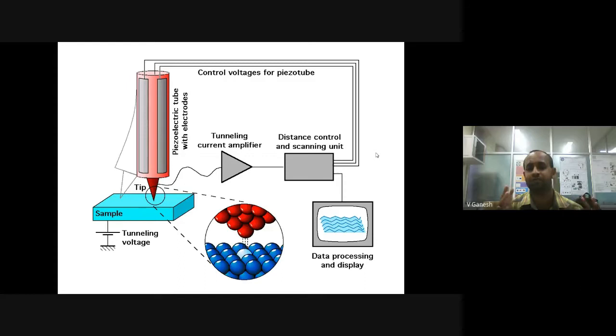If you connect the probe along with this piezoelectric tube, which has four different quadrants, you can apply a positive voltage on two quadrants, causing the tube to shrink so the probe moves forward. You can control the movement precisely at the nanometer scale using such voltage. When you reverse the polarity and apply a negative potential, the piezoelectric tube expands, and the probe is retracted back. That's the advantage of using piezoelectric material—it allows one to control the movement of the probe towards the sample substrate.